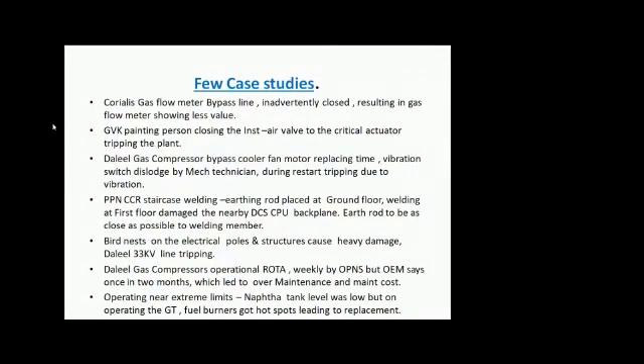Similarly, one of the gas compressors had a gas cooler fan with vibration. So the mechanical and electrical team started working on it, removed the fan, removed the bearings, and replaced everything back. While starting again, they saw the vibration was high and the machine was not starting. Finally, what happened is that while removing the fan, they didn't take the instrument person with them, so they disturbed the position of the vibration switch, because of which it was giving high vibration while starting and was not starting. It was understood only after a lot of study and mind-boggling effort.